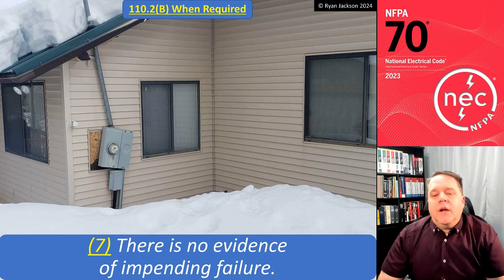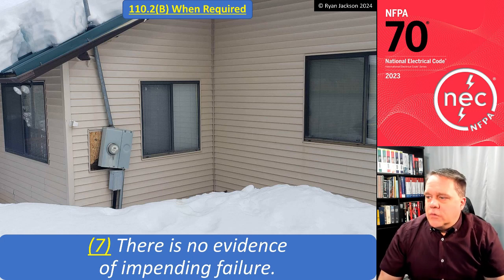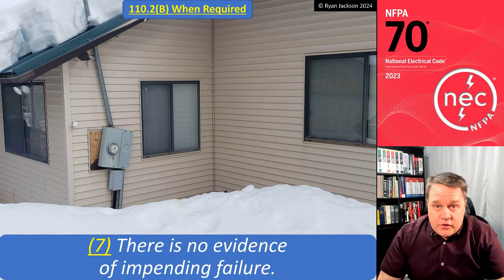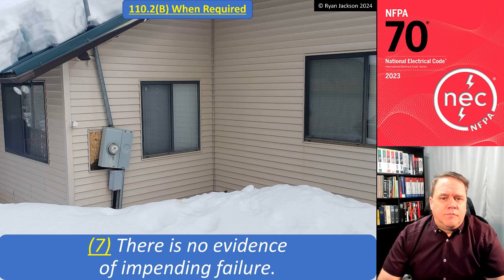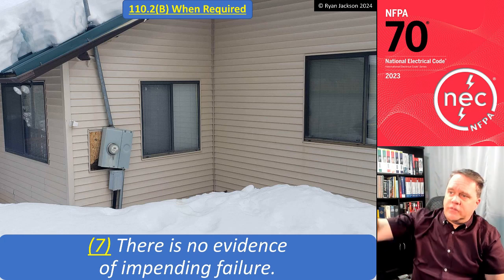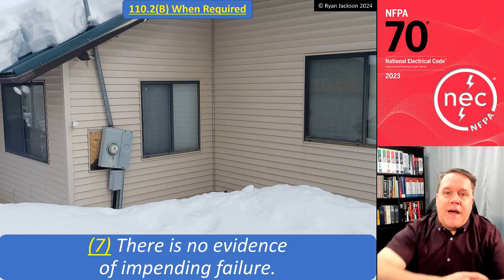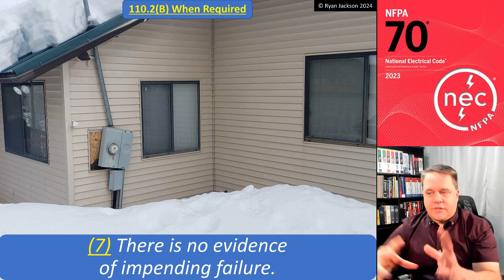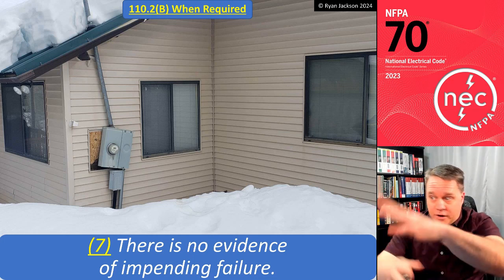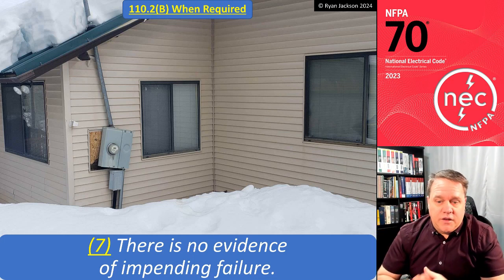Item 7, there needs to be no evidence of impending failure. All right, so here we have this panel board on the outside of a dwelling unit. And you can see that the snow has completely destroyed it, right? This massive snowstorm, 3 feet of snow, took the mast right off the roof, racked the equipment out of square, and now it looks like this.